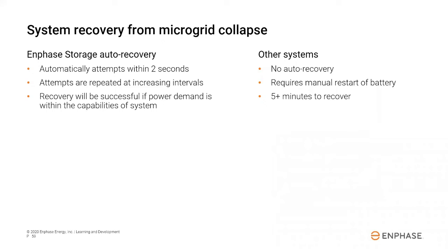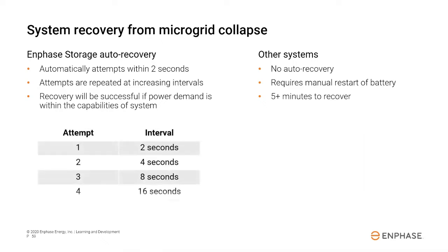Enphase storage does rapid auto recovery in the event that the microgrid gets overloaded and shuts off. There may be times when the power demand of a home overwhelms a battery storage system, even with features like Enphase Power Start. In these situations, an Enphase storage system will automatically attempt a system recovery within just 2 seconds of the collapse. And if unsuccessful, it'll make repeated attempts with increasing time intervals. Once the power demand of the home is within the capabilities of the system, the recovery will be successful.